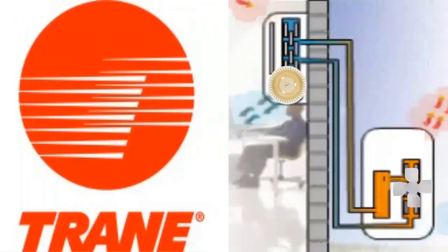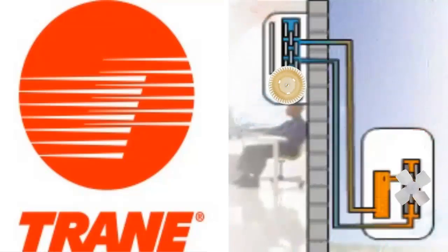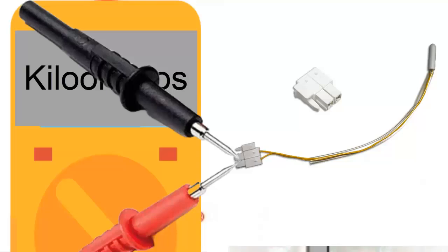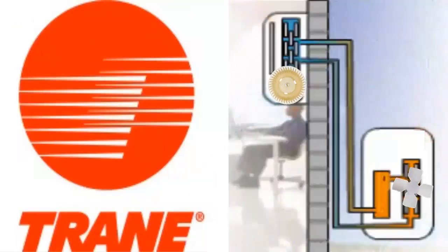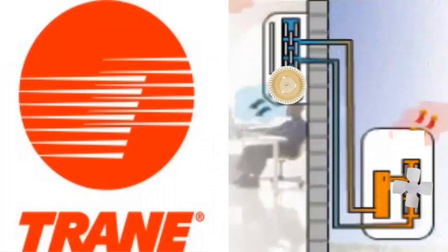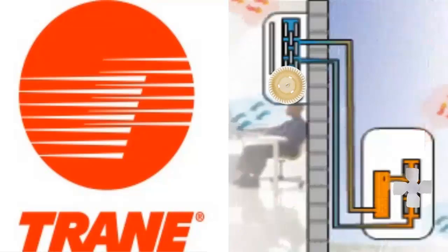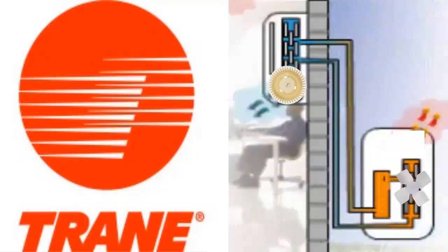F. The resistance value should never be 0 or infinite. G. With the sensor connected and the electronic board powered on, measure the voltage supplied by the board with the multimeter set to the DC voltage scale. This value should be close to 2.5 volts. Now, let's look at the fault codes related to temperature sensor issues generated in TRANE equipment.